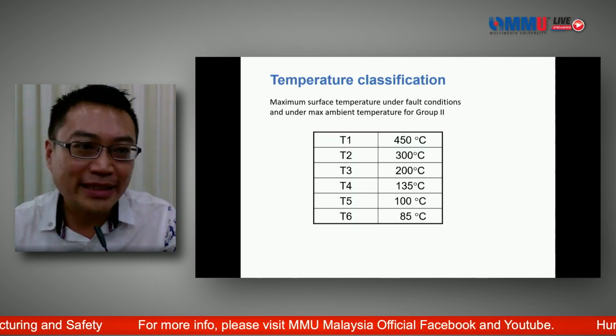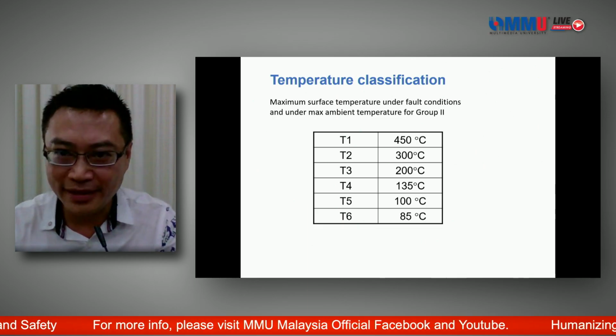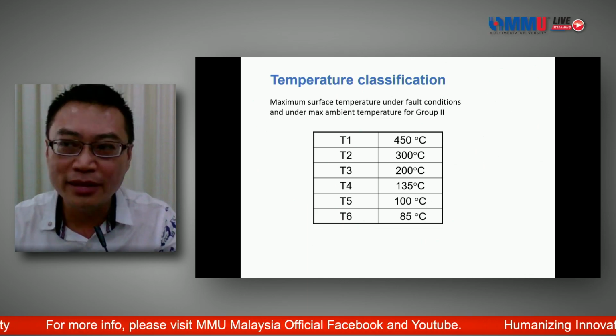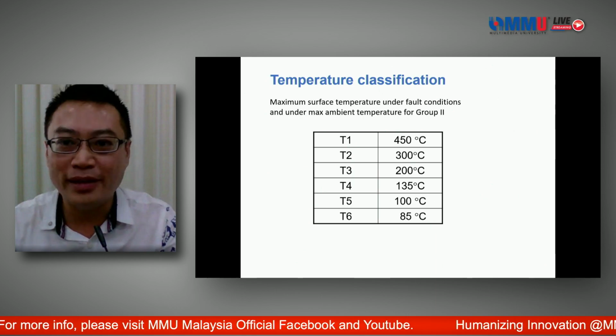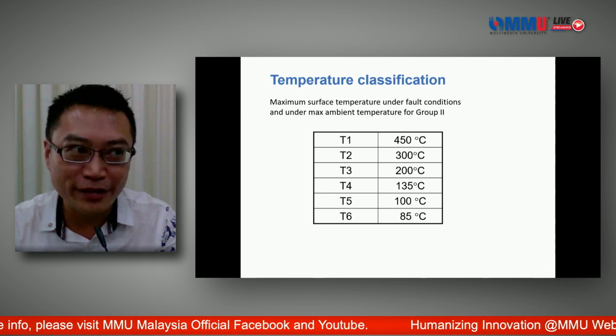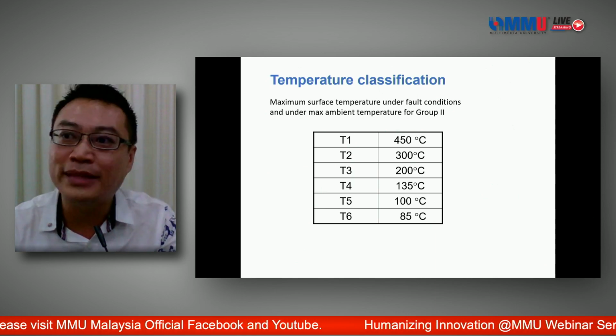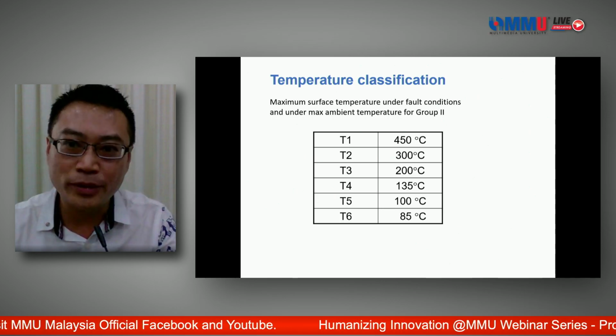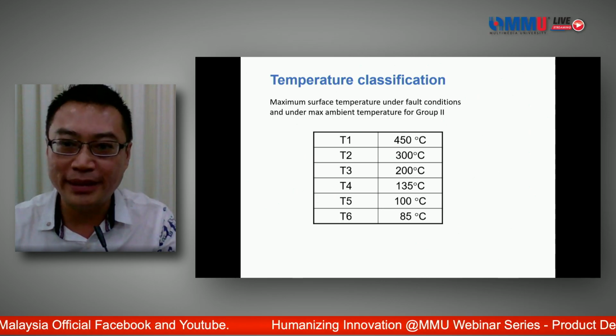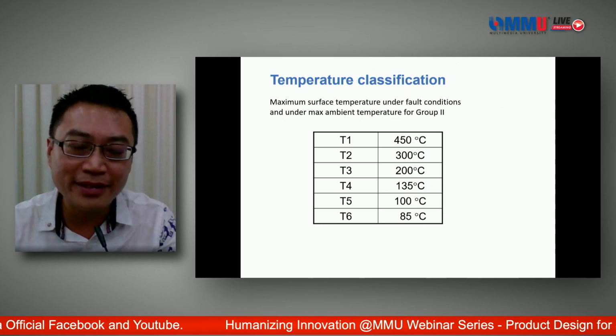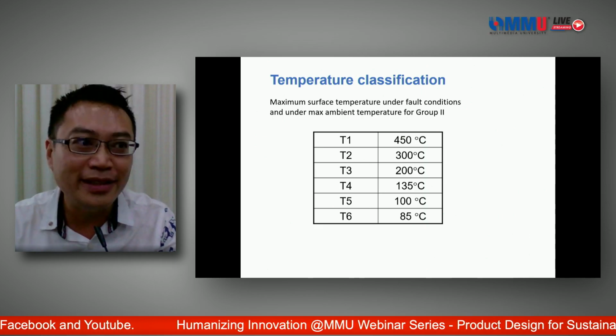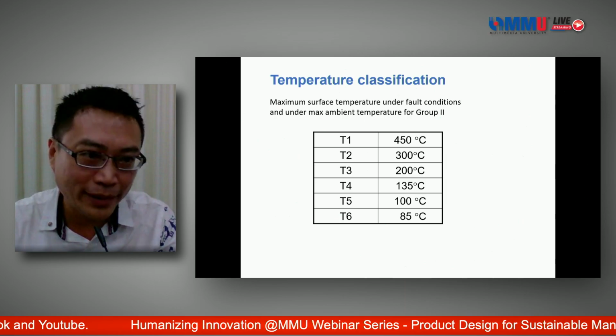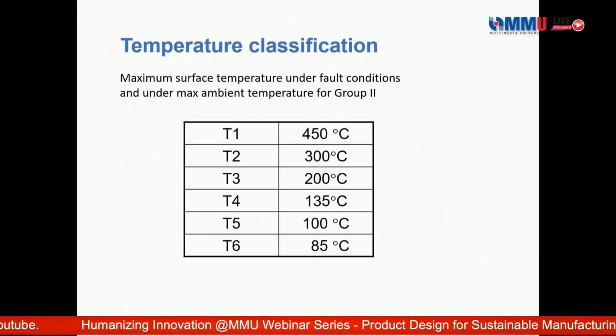The last thing I want to talk about for safety is temperature classification. A T1 will have protection against 450 degrees Celsius, the maximum temperature the device can get to, and T6 would be 85 degrees Celsius. That means T6 is actually a lot more protective than T1. You can hardly design a product that meets 85 degrees Celsius because your ambient temperature could be very hot.